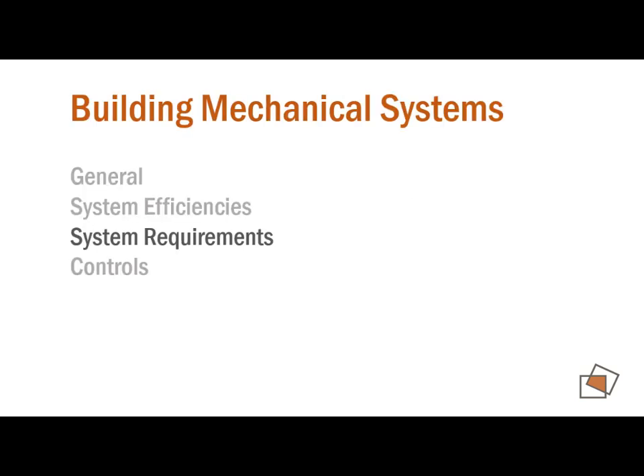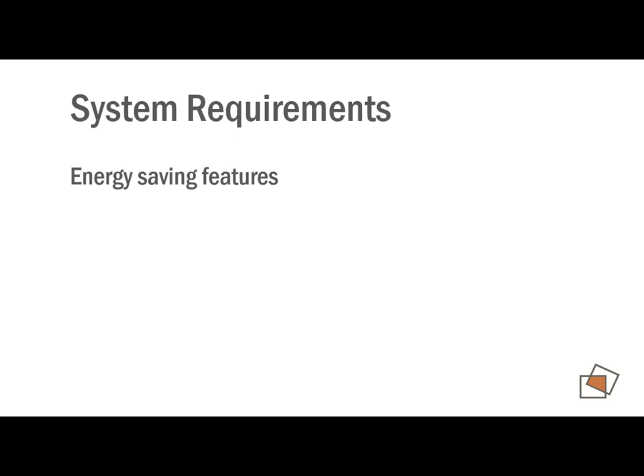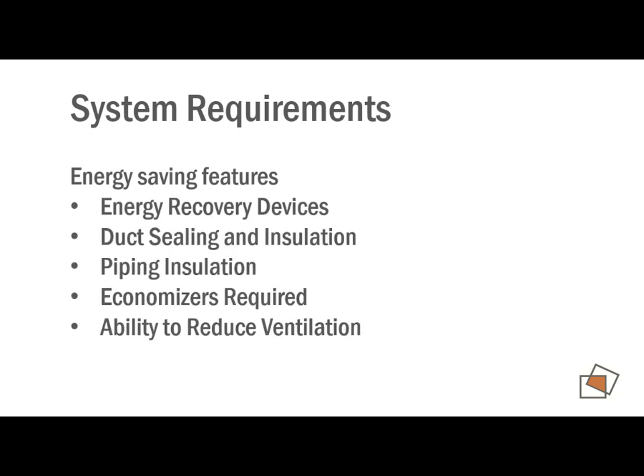So the additional requirements that the code spells out for the mechanical system are, I kind of see it, 2 things. They have energy saving features that are specified, and that's your heat wheels, your duct sealing, insulation type requirements for piping insulation, economizers in certain applications, and the ability to turn down your ventilation air when it's not needed. So these are energy saving features that are required in the mechanical system. Economizers is a thing to be mindful of.